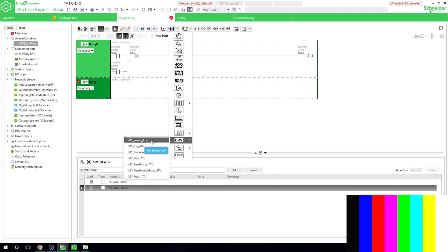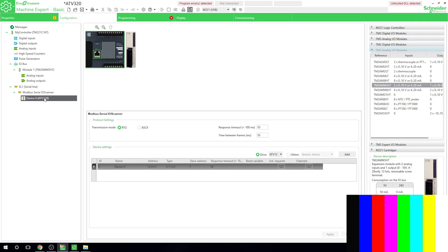Let's create our first rung. We need to enable our drive, so we're going to use the MC_Power_ATV function block — grab that and add it in. It shows red because the axis isn't set up yet; it's looking for which drive to use. You can add up to 16 drives on this particular network. Select Drive 0 and click Apply — that's the drive we set up last time. You can verify by going into Configurations and checking that the drive address is 0.